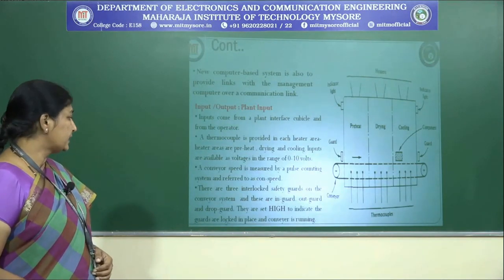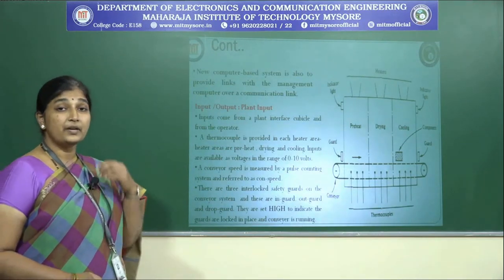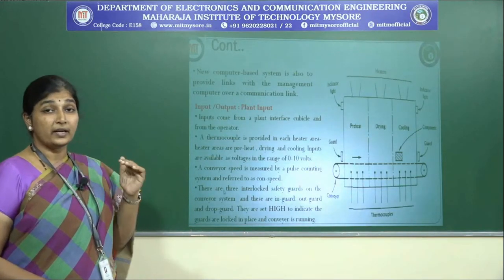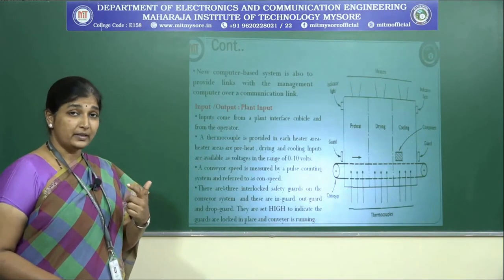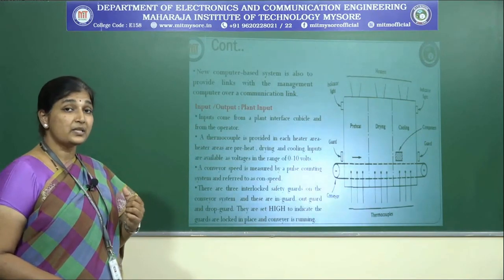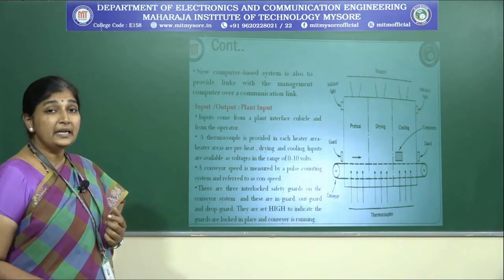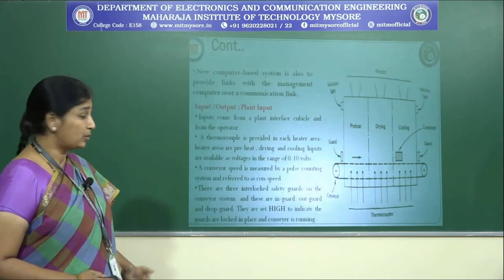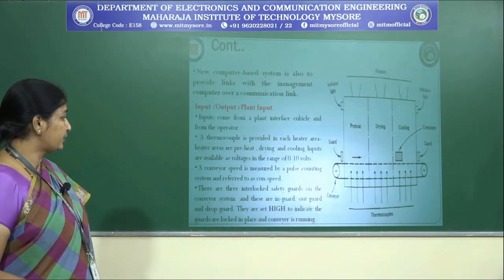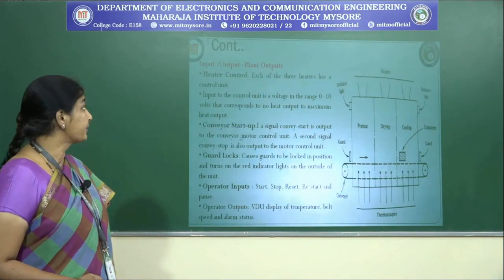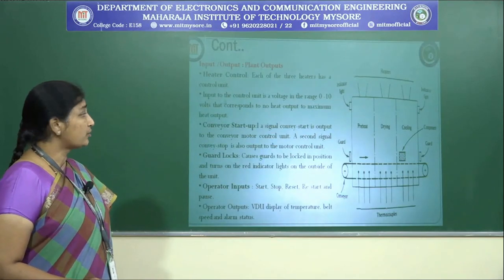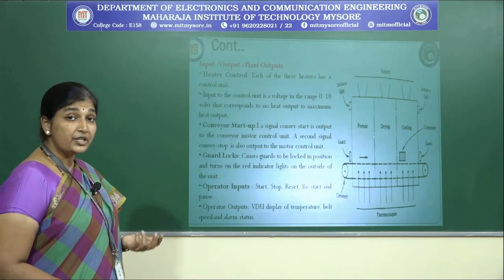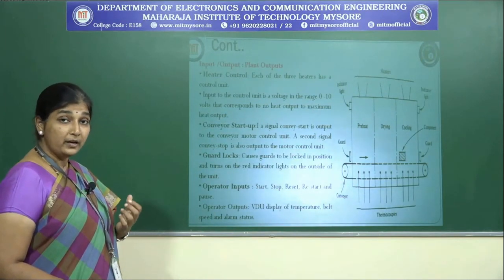The guards are set high to indicate that they are locked, placed, and the conveyor is running. When all three guards are set high, the conveyor belt is running and an indicator turns red. If the signal is low, it means the conveyor belt is not moving. Each of the three heaters has a control unit to control the temperature and voltage. Input to the control unit is a voltage of 0 to 10 volts, corresponding to no heat output to maximum heat output.